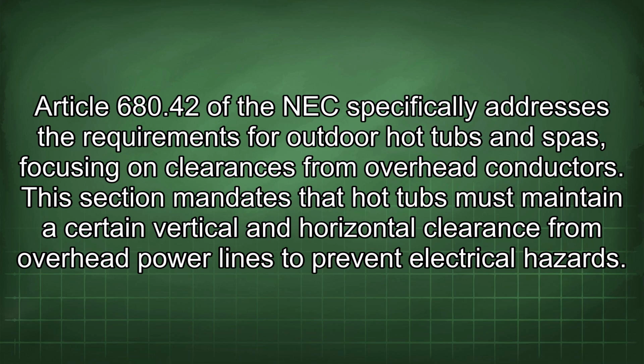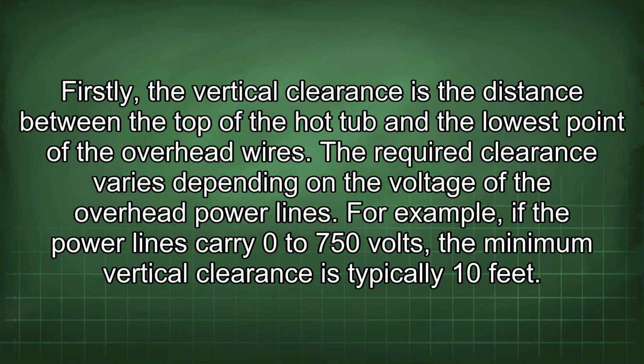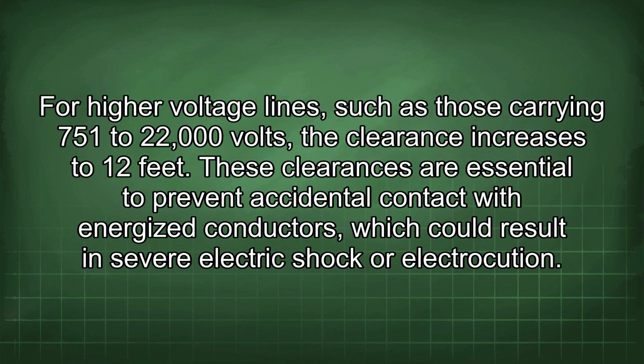prevent electrical hazards. Firstly, the vertical clearance is the distance between the top of the hot tub and the lowest point of the overhead wires. The required clearance varies depending on the voltage of the overhead power lines. For example, if the power lines carry 0 to 750 volts, the minimum vertical clearance is typically 10 feet. For higher voltage lines, such as those carrying 751 to 22,000 volts, the clearance increases to 12 feet. These clearances are essential to prevent accidental contact with energized conductors, which could result in severe electric shock or electrocution.